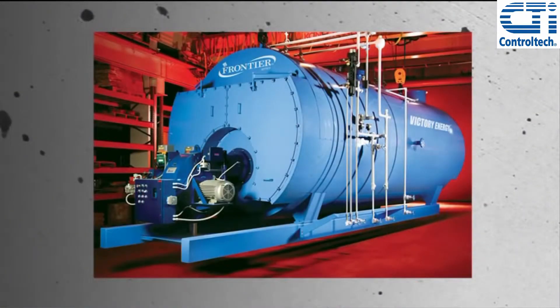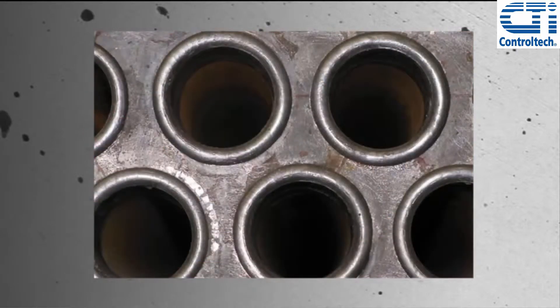The metal thickness of these boilers plays a very important role in the design layout for different pressure ratings. All ASME Code Section 1 fire tubes with pressure design ratings of 250, 300, 350, and even 400 PSI will have to meet the thicknesses for maximum safety factors.